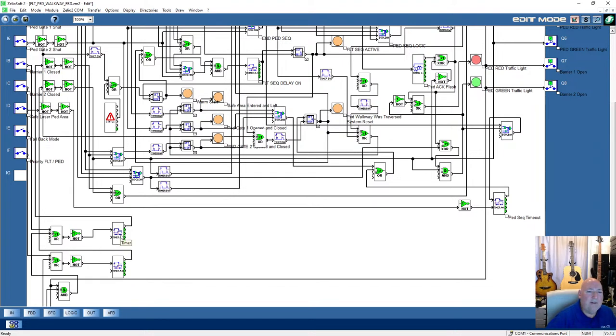On delay, it's inverted, so it'll be the other way around, right? I think we need, let's try a 3 second on delay. This might be the wrong way around. So, 3 seconds to open. Oh, we're in this mode. So, 0.01 of a second, so that's 3 seconds, I think. Same with this one.